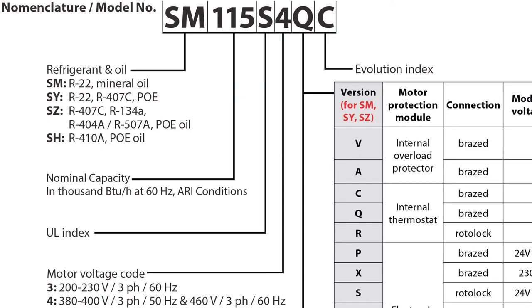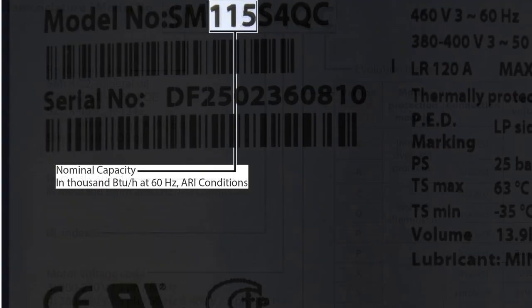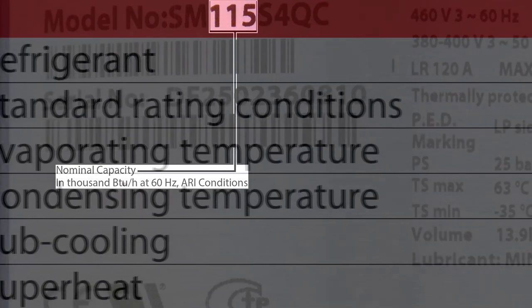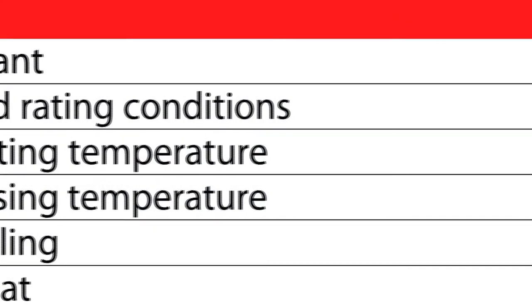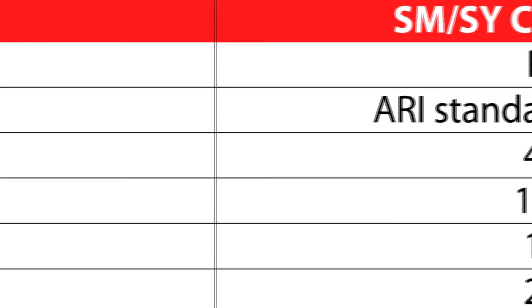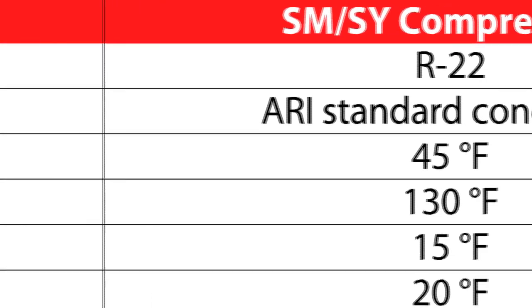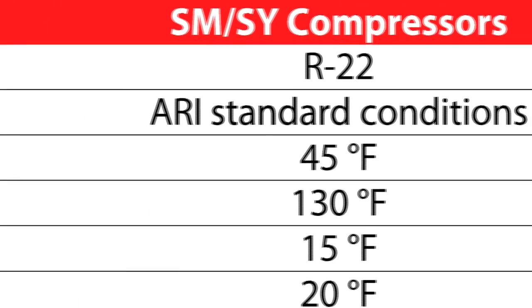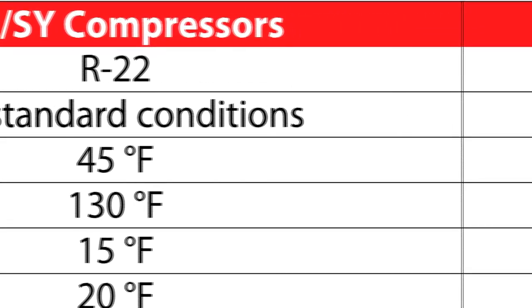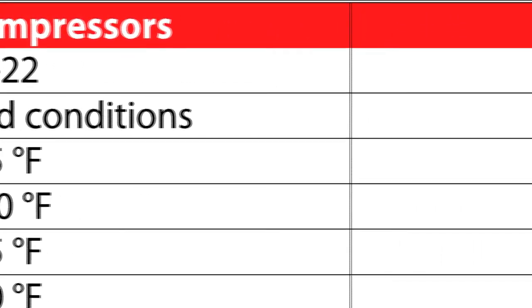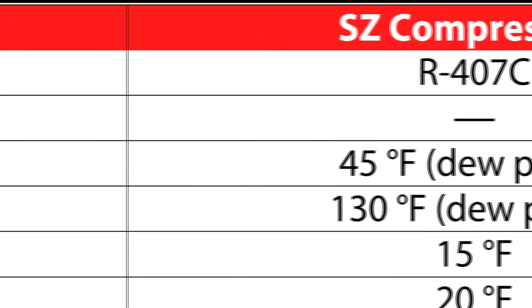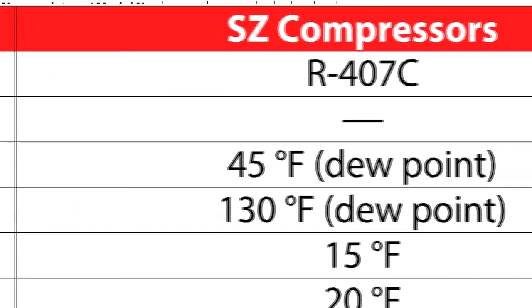The next three digits of the model number signify nominal capacity of the compressor in thousands of BTUs per hour. As seen in this table, the nominal capacity is determined using standard ARI conditions, with 45 degrees Fahrenheit for the evaporating temperature and 130 degrees Fahrenheit for the condensing temperature.